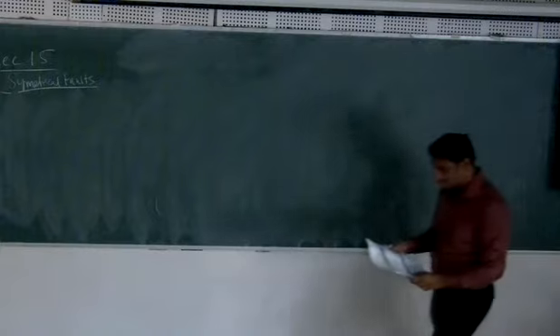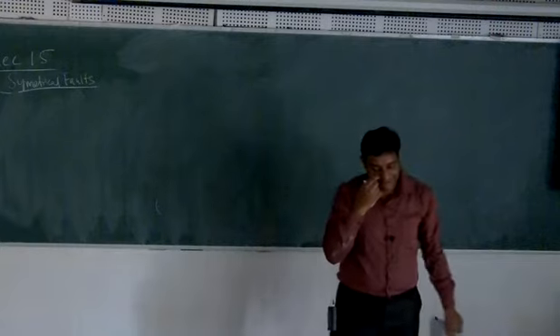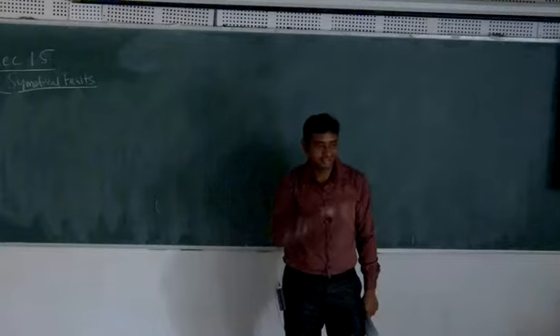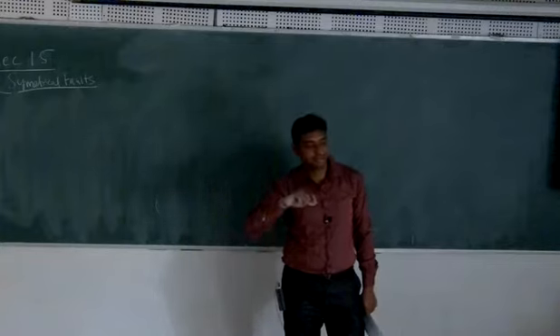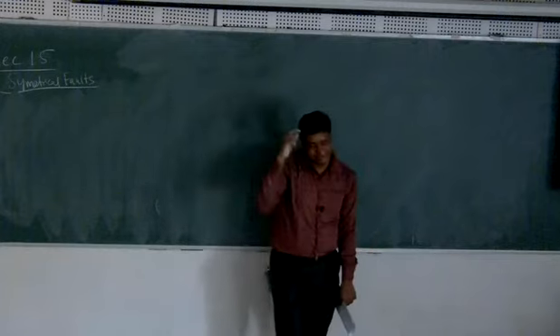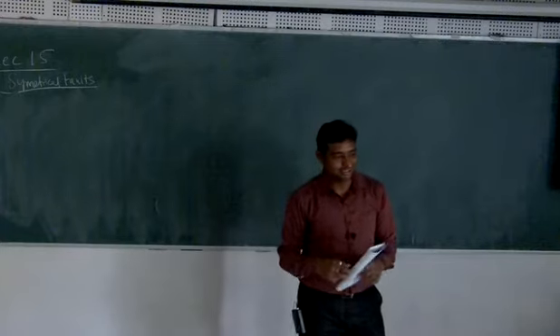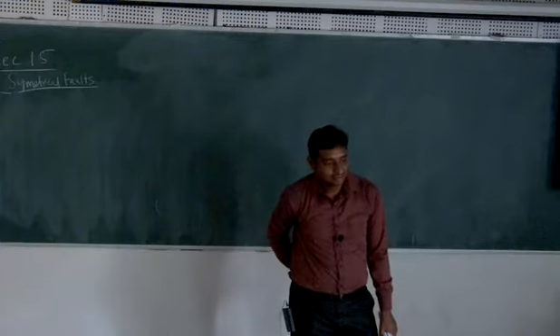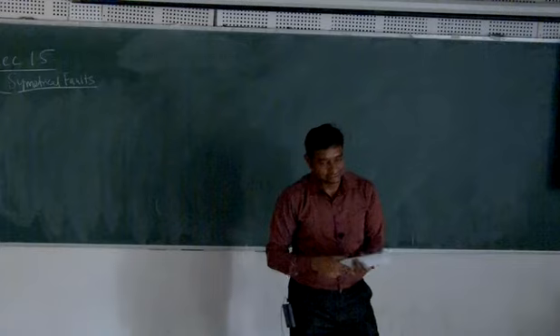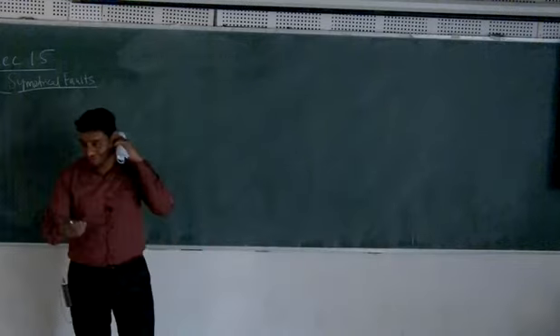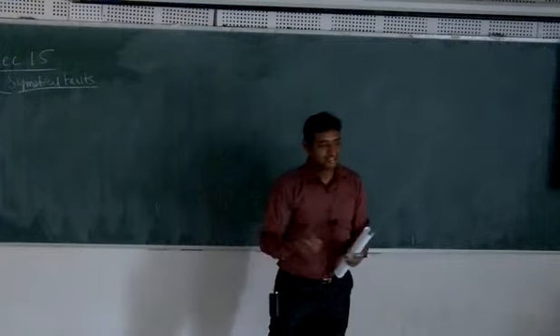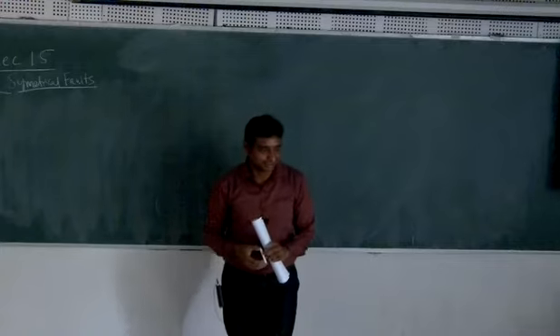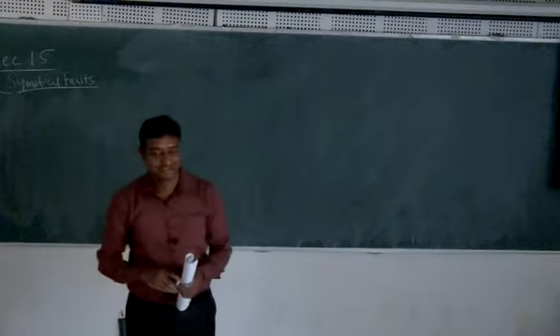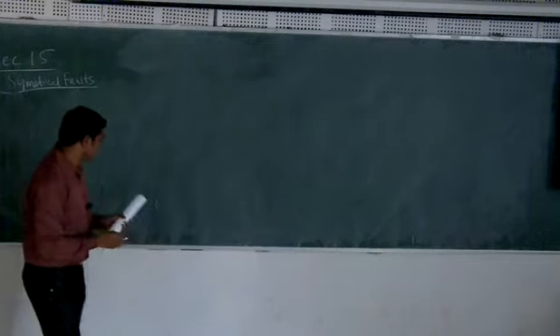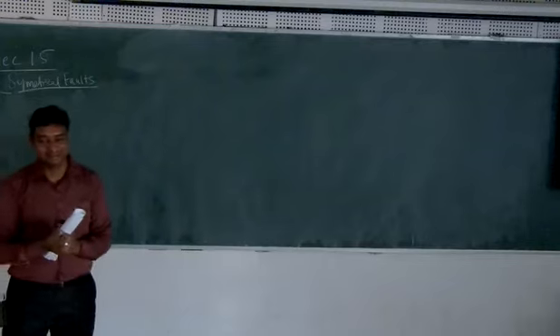The question is why do we assume 1 angle 0 per unit? In a normal case you should not do that. You should solve the load flow problem first, and from its results you get the voltage magnitude and angle, which you should use for the rest. We are doing this here because we are only interested in understanding the concept. Another reason is that normally the voltages will be less, but when I want to design the circuit breaker, I want more current so that my design is safer. You can do it accurately, but for the purpose of designing a circuit breaker's rating, you can directly take 1. Most of the time, assumptions like these are made to simplify.